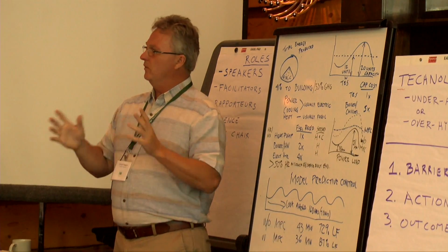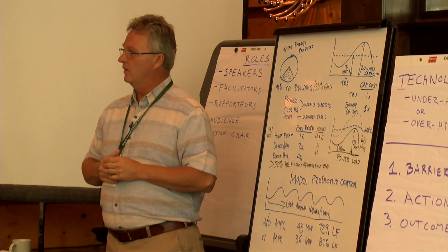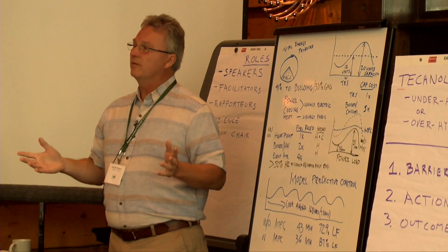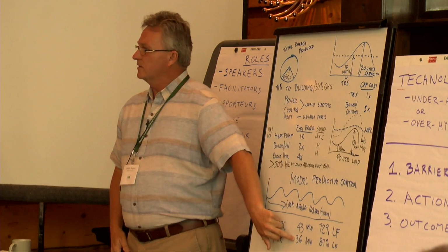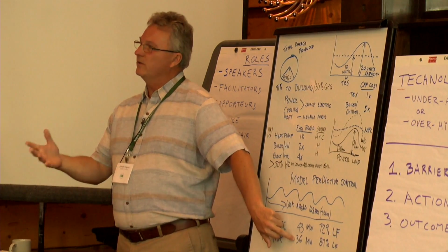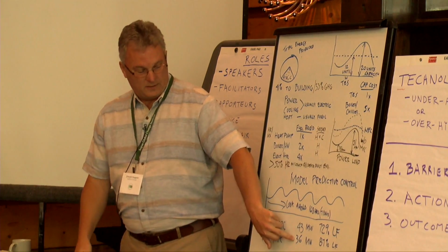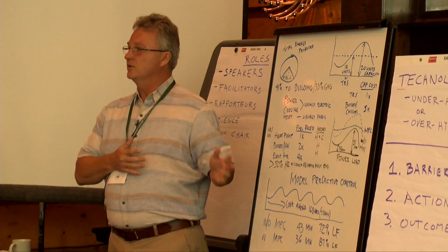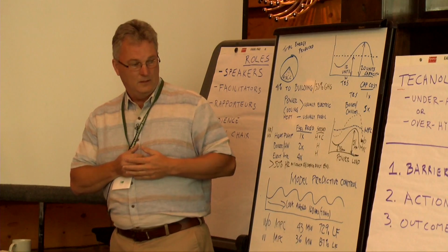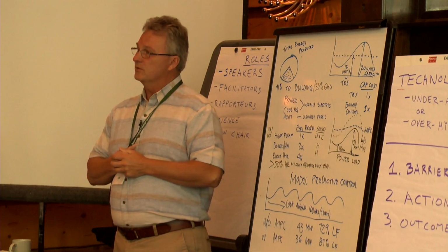When the cogen plant went down for maintenance, there was a grid impact at Stanford of 46 megawatts. We have now electrified the entire system, and our impact is 36 megawatts. Who thought possible that you could electrify an energy system for a city or a campus and actually lower your impact on the grid through use of thermal storage and smart controls and software? So that's in a summary where I see the big benefits of thermal storage.